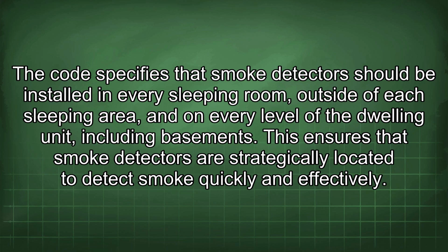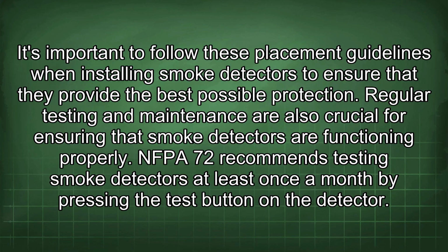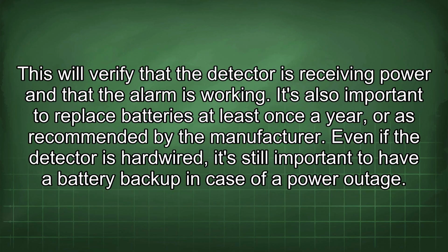This ensures that smoke detectors are strategically located to detect smoke quickly and effectively. It's important to follow these placement guidelines when installing smoke detectors to ensure that they provide the best possible protection. Regular testing and maintenance are also crucial for ensuring that smoke detectors are functioning properly. NFPA 72 recommends testing smoke detectors at least once a month by pressing the test button on the detector. This will verify that the detector is receiving power and that the alarm is working.